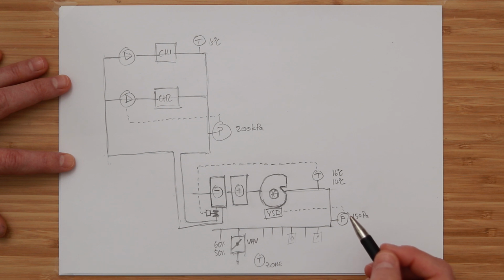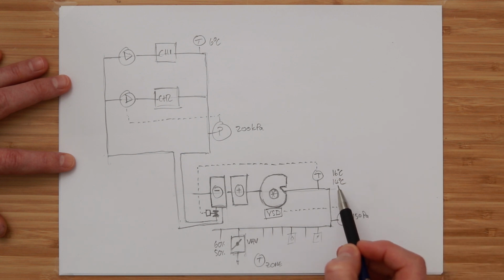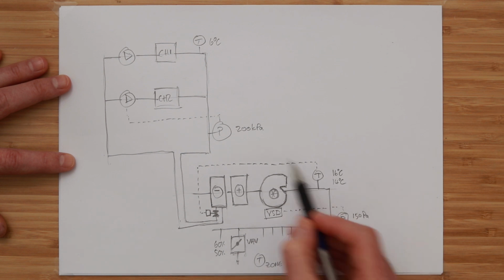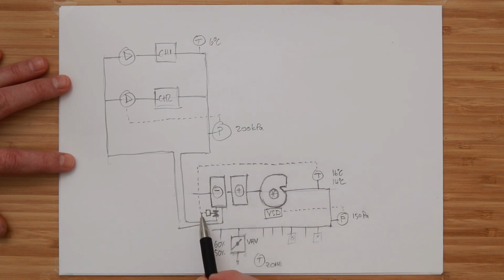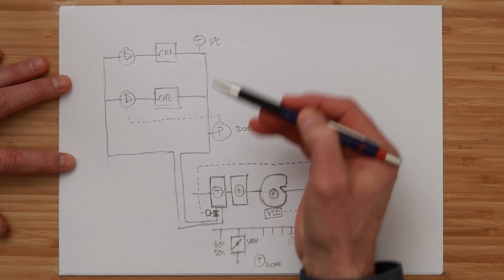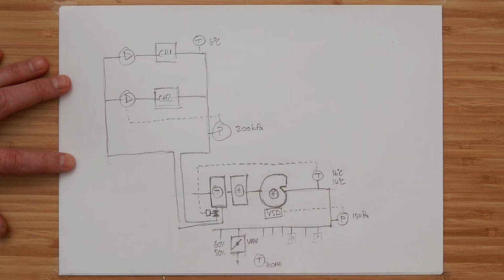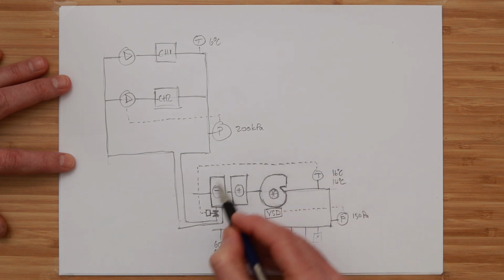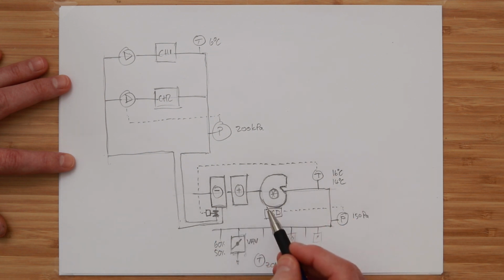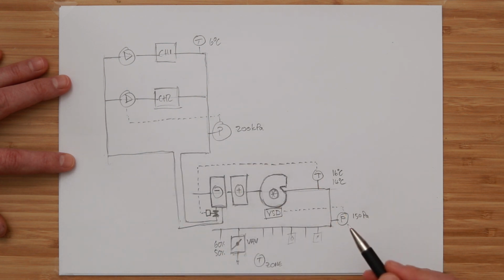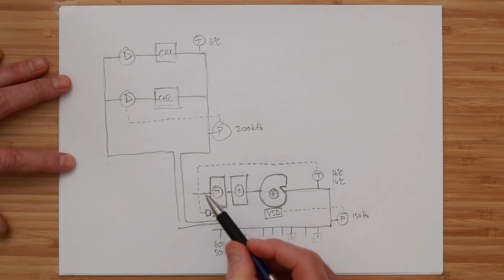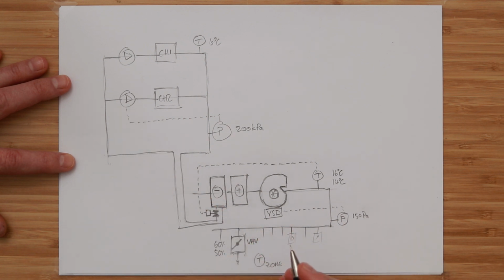The problem we have is that obviously as we drop this air handling unit supply temperature down slightly, the cooling valve opens and all these AHU cooling valves open a little bit more. And as that happens, the chilled water pipe pressure drops and the variable speed drives on the chilled water pumps speed up. So as we're optimizing this system and saving fan energy, there is a negative impact somewhere else in a different plant room that we're not looking at because it's resulting in our chilled water pumps speed increasing and using more pumping power to get more chilled water around here. So just put that in your head for a second, or put that just to one side for a second.